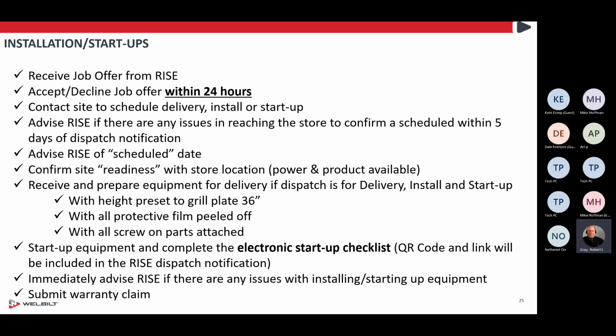All right. One thing you want to make sure of if you're doing it before you plug in that AC grill is to cut the zip ties for the conduits. They are zip tied to the guide loop in the back of the unit. Once you plug it in and you turn on that single main power switch, the first thing that UI is going to do for each lane is go through initialization. It's going to want to see those platens in the open, ready state. So if they're down, guess what's going to happen? It's going to send power out to the actuator motor, and it's going to send them up. If those zip ties are still on the conduit, you can actually break the conduit or break some wires inside the conduit. So keep that in mind, cut those off.